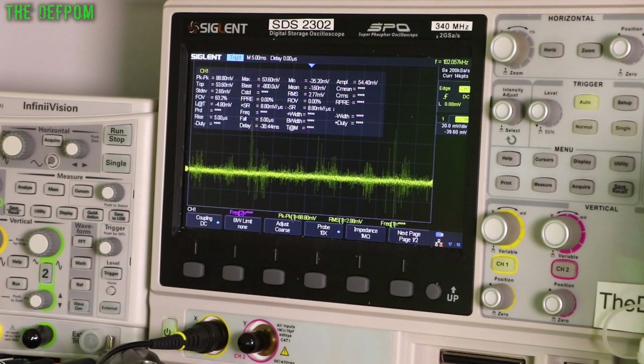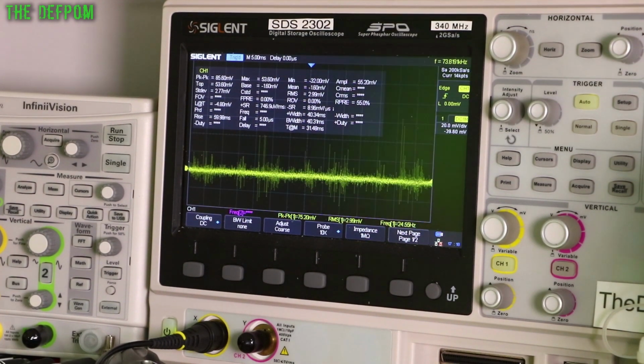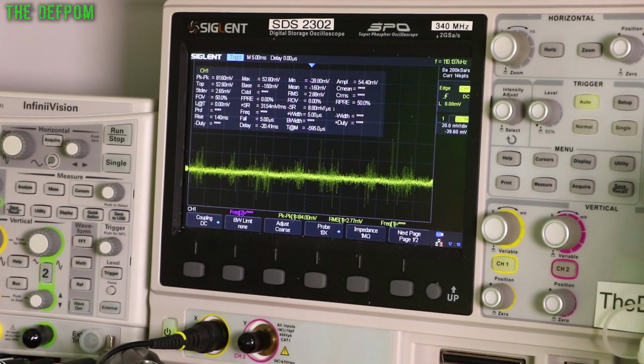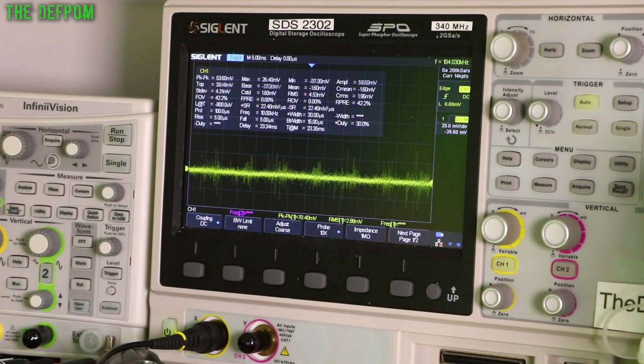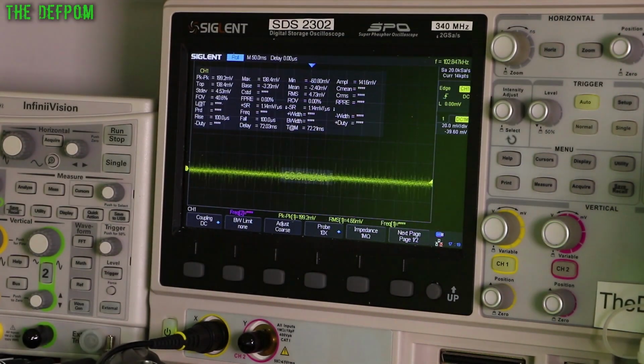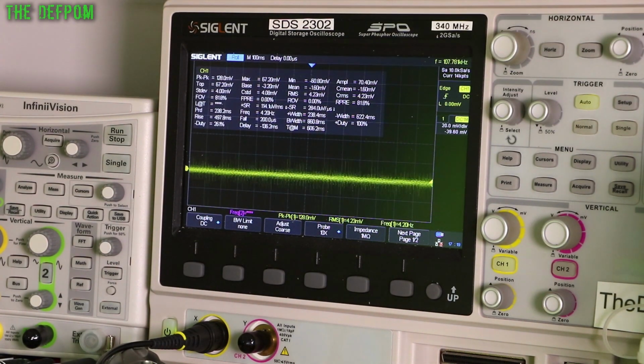And as you can see, it's a nice noisy waveform, and that's what it does mention in the manual. Now I've got to set this for 0, a noisy waveform around the 0 point. It looks like it's pretty much there, but this is for R20. Let's give it a tweak. Nothing really changing. Don't really see anything changing there. I know I'm on DC coupling as well. I think it is affecting the noise. The noise is getting smaller. You probably can't see it on camera because it's scrolling so fast.